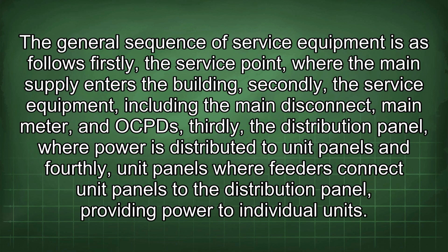The general sequence of service equipment is as follows. Firstly, the service point, where the main supply enters the building. Secondly, the service equipment, including the main disconnect, main meter, and OCPDs. Thirdly, the distribution panel, where power is distributed to unit panels. And fourthly, unit panels, where feeders connect unit panels to the distribution panel, providing power to individual units.